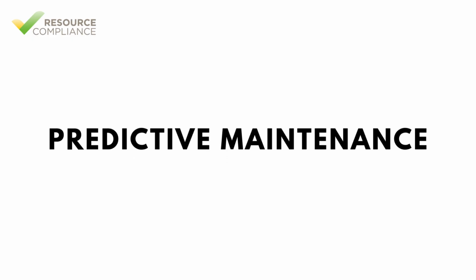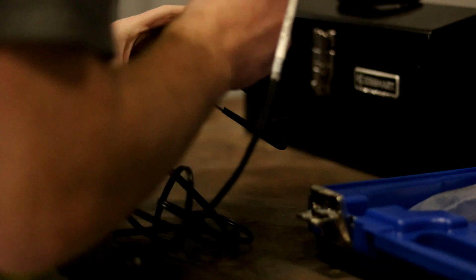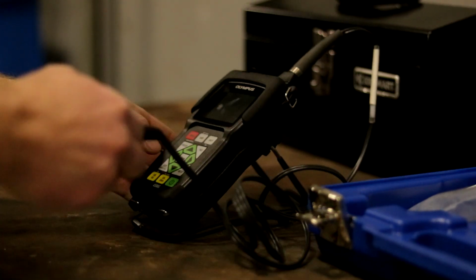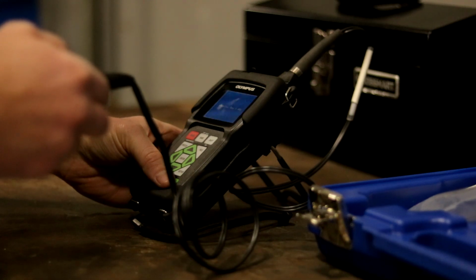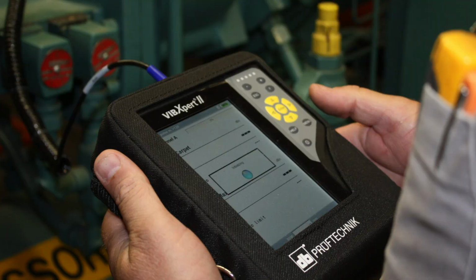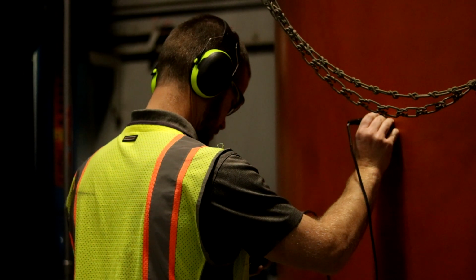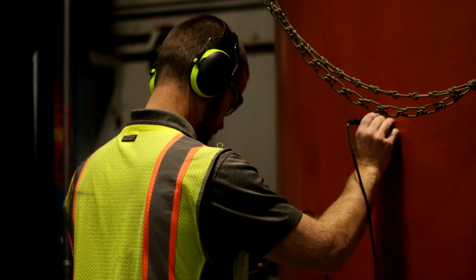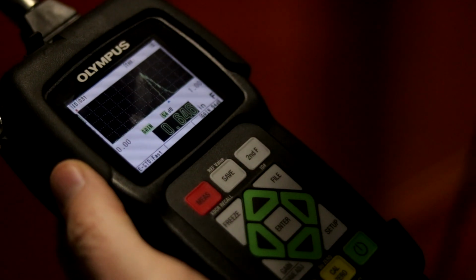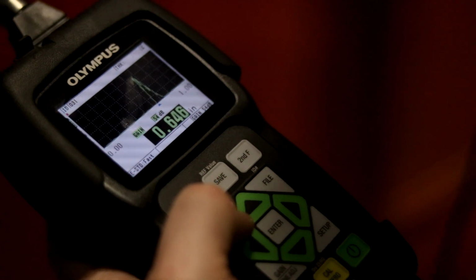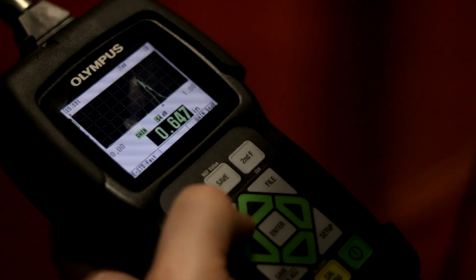Predictive maintenance is a less familiar term, but one all operators should be familiar with. Predictive maintenance utilizes measurements to detect the onset of equipment failure prior to any noticeable degradation. In the refrigeration industry, ultrasonic thickness testing, vibration analysis, and oil analysis are examples of predictive maintenance. Predictive maintenance is exceptionally useful at identifying issues while they are still small and less expensive. In other words, predictive maintenance helps to reduce the occurrence of catastrophic failures.